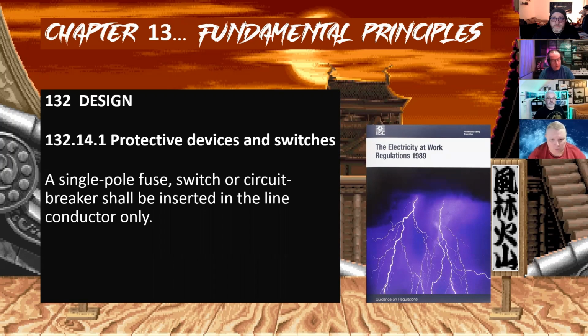Okay, next - John. So this is 132.14.1, protective devices and switches. A single pole fuse, switch, or circuit breaker shall be inserted in the line conductor only - so no switching the neutral and leaving the rest of the installation energized and in a dangerous condition.